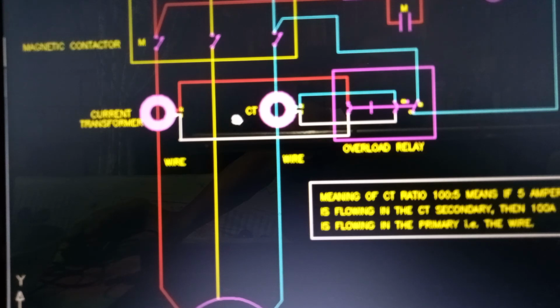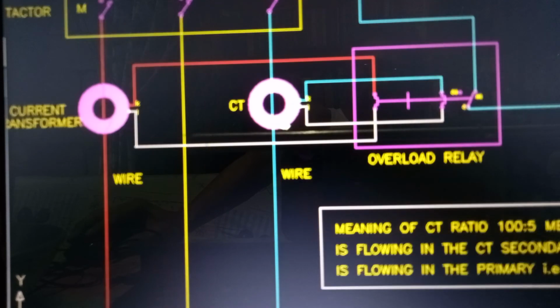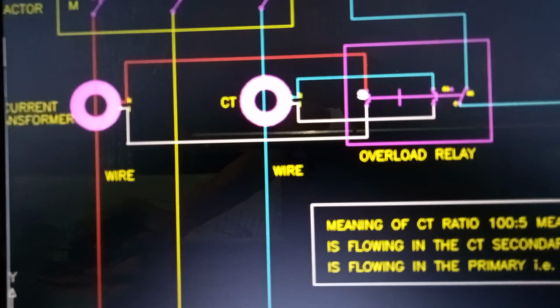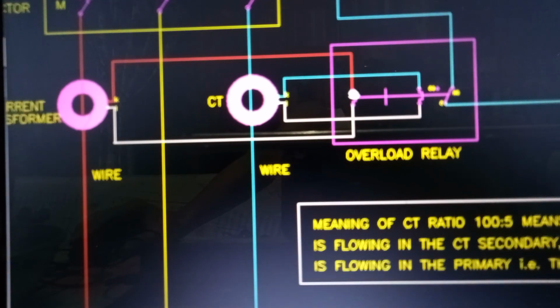So that is the purpose of why we are using a current transformer, to reduce the current flowing to the overload relay. For example, even if the current in the primary is 200 amperes and you are using a 200:5 CT ratio, then only 5 amperes can flow into the overload relay.